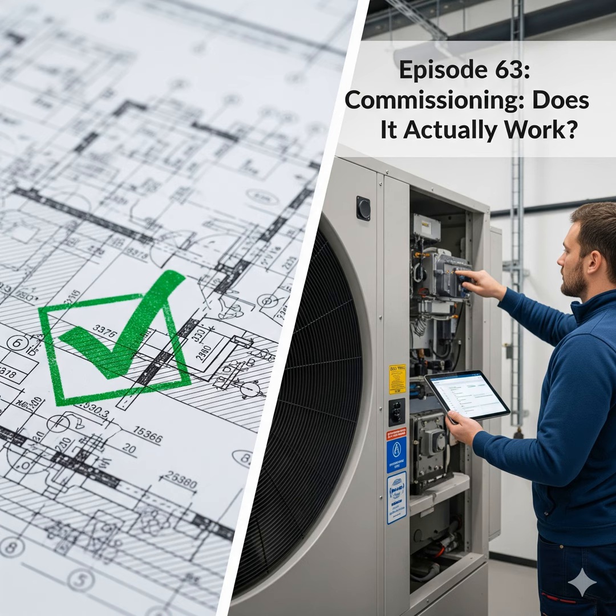Imagine finding a major design flaw like an undersized chiller plant, a misaligned duct system, a controls incompatibility, finding that in a digital model review or during early functional testing, rather than after the walls are up, concrete's poured, and the system's supposedly operational. Yeah, the cost difference must be huge. It's exponential. Fixing an error on a computer screen versus tearing down and rebuilding a physical system. There's no comparison. It's about preventing those costly problems that lead straight back to that nightmare scenario you described at the start.